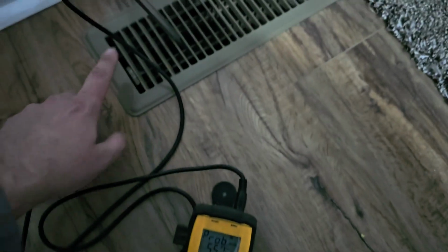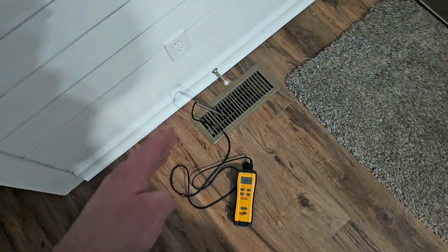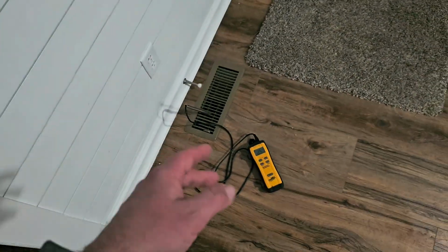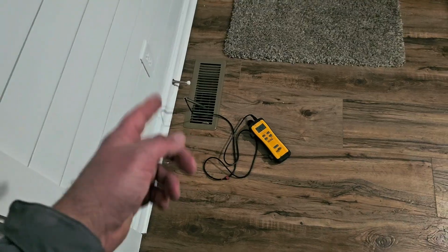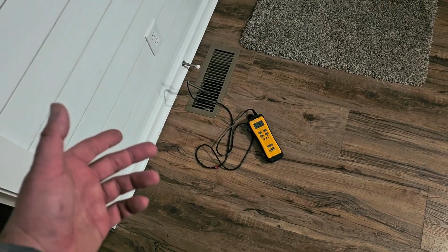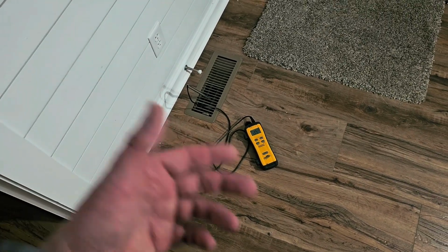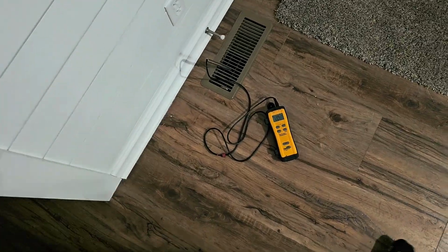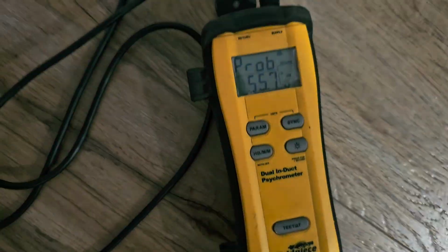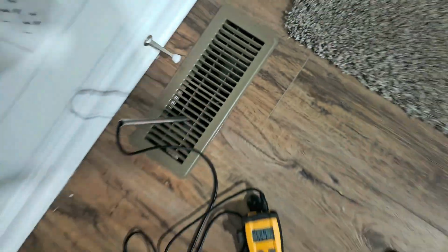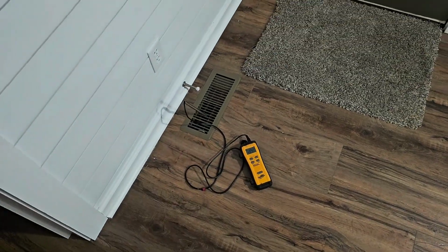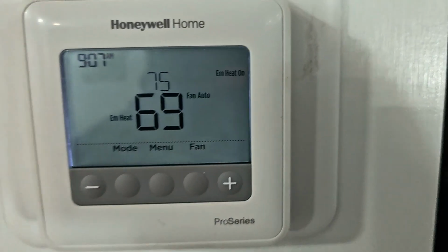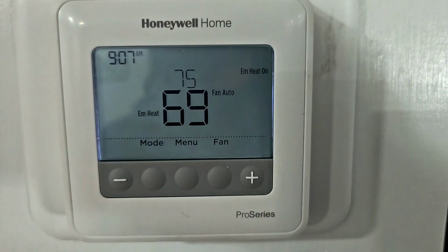And once it kicks on, we're going to make sure that this temperature is at least 20 degrees warmer than the thermostat. It should be more than that. So if it's 69, it should be blowing at least, I would say, 90 at least. So we're gonna leave this in here. Fan's not blowing yet. We're gonna check out that temperature. Emergency heat is on now. So you can see it's no longer flashing.